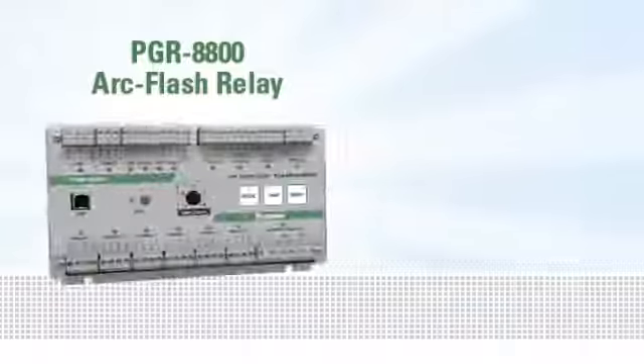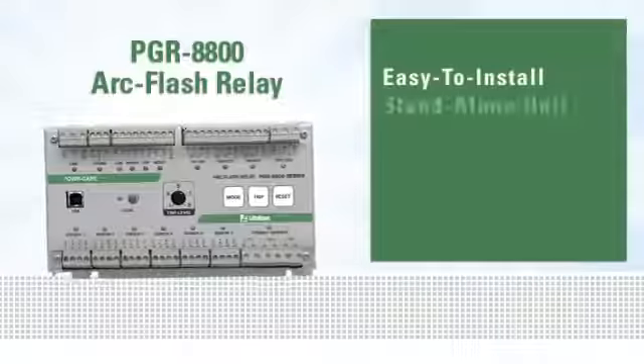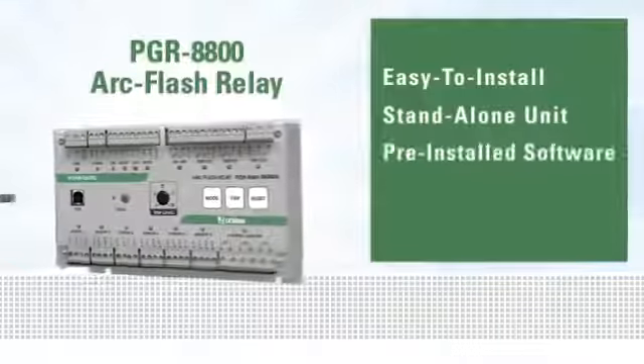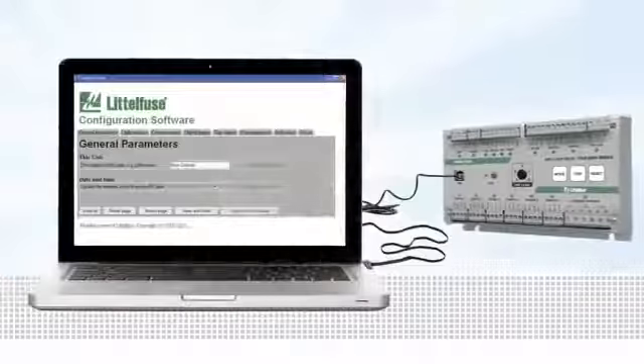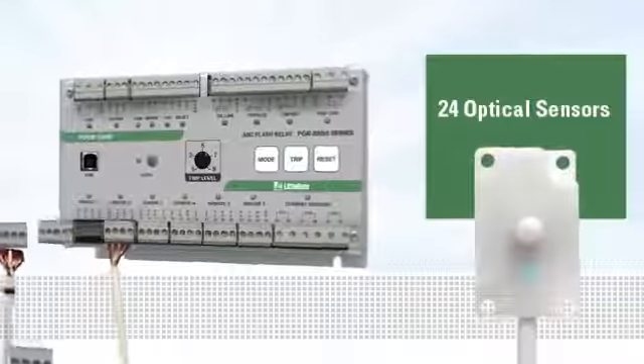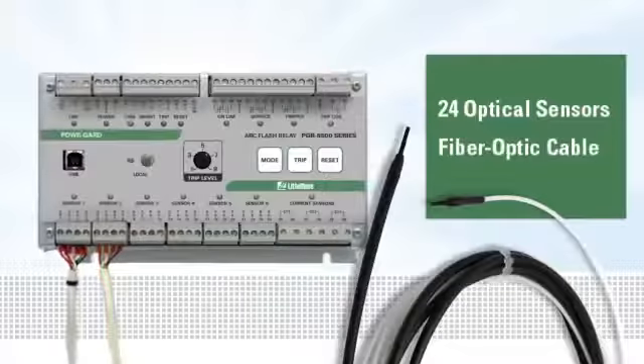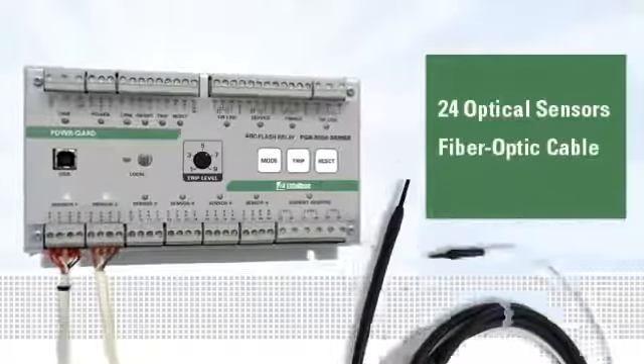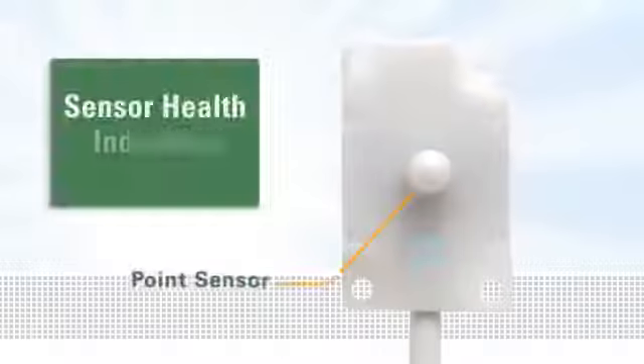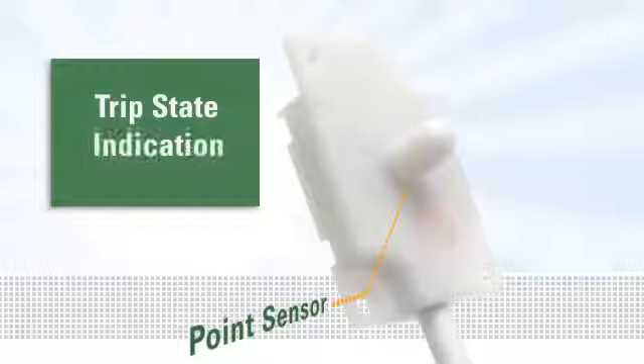The Littelfuse Arc-Flash Relay is an easy-to-install, standalone unit with pre-installed software. And it offers up to 24 optical sensors, as well as the option to use a fiber-optic cable for those difficult-to-reach compartments. Each sensor is equipped with an LED light to indicate both sensor health and trip state.